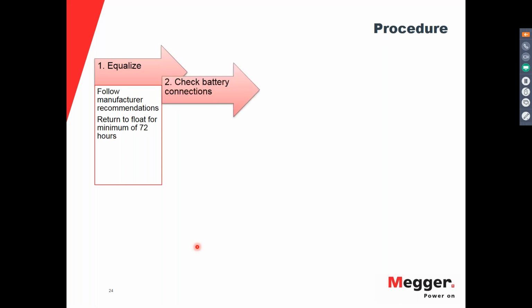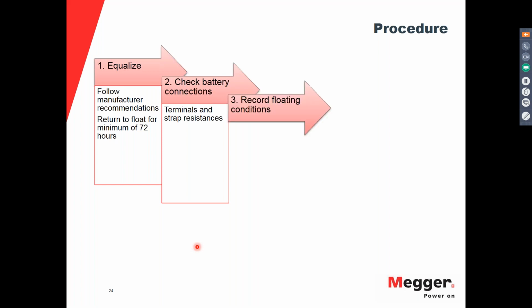The second step is to check the battery connections. So you want to check all the terminal resistances and the strap resistances, and you want to perform maintenance on them if you see something that is not good. Now, if you just want to see how your maintenance procedures are affecting or improving your battery, probably you don't want to do this prior to the test, because you want to see how things are in real life, not with a battery fully prepared.